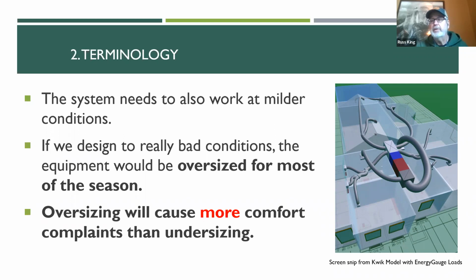And another thing too is that it's very commonly known that load calculations are actually higher than what the load really is in the house. I guess you'd say they're playing it safe. There are some safety factors built into the load calculations. And then people get nervous and add another safety factor on top of that and round up to the next size. And the next thing you know, your equipment's too big and you're having comfort complaints. And people think, I must have undersized it, and then they make it bigger the second time. And so it evolves for equipment to get bigger and bigger, but we're trying very hard to encourage people to go the other direction.